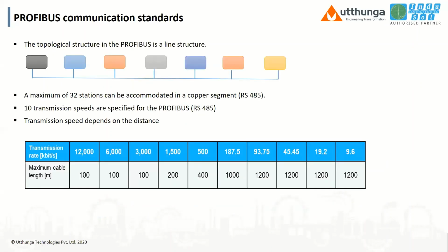So, coming to Profibus communication standards. Topology, as we know, is serial. It's a line structure, a daisy chain. And in a segment, since it is RS485, you can have a maximum of 32 stations only. You can have 10 transmission speeds, and the maximum speed you can run in Profibus communication is 12 Mbps. Speed is always dependent on the length. Like at 12 Mbps, you can only go up to 100 meters. At 9.6 kilobits, you can go up to 1200 meters.